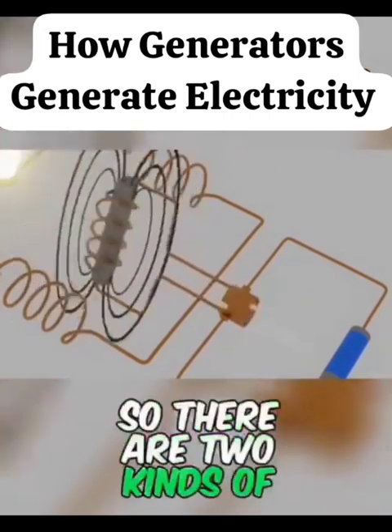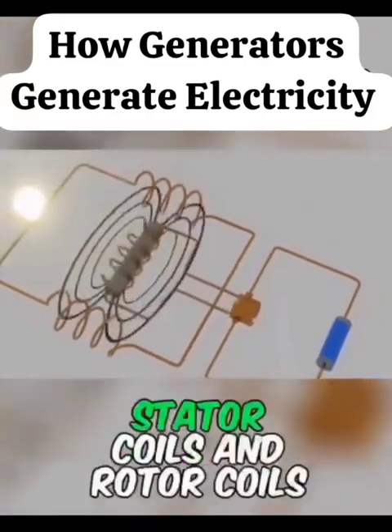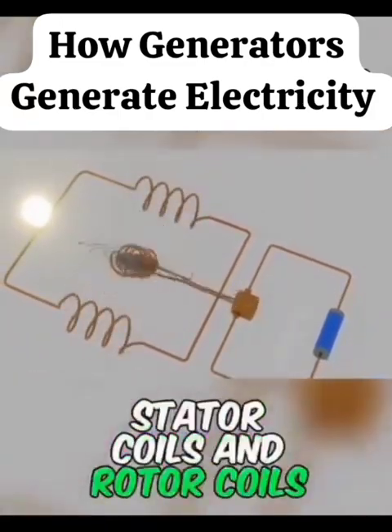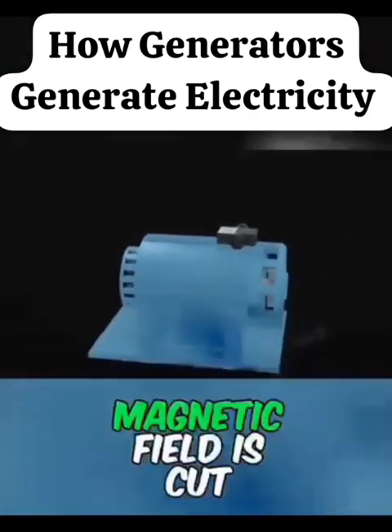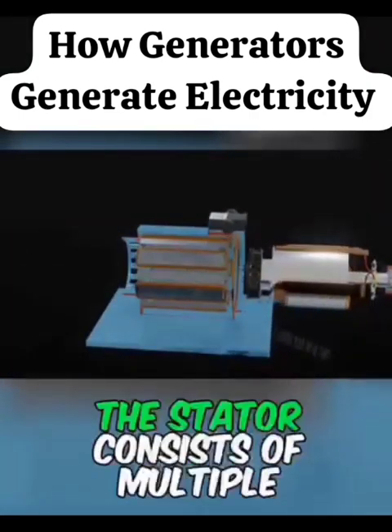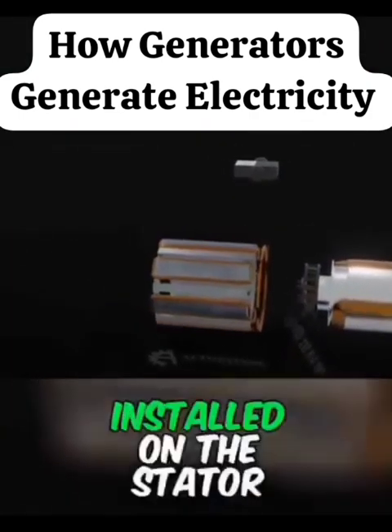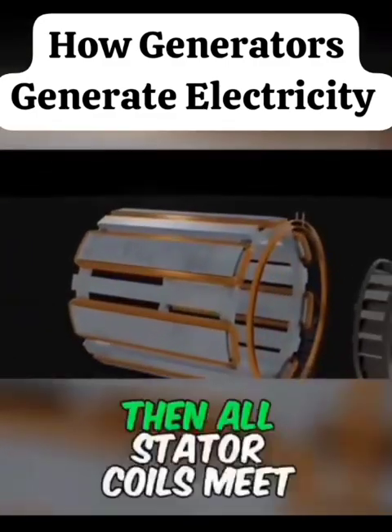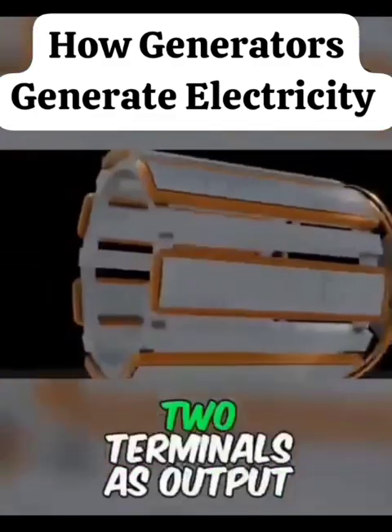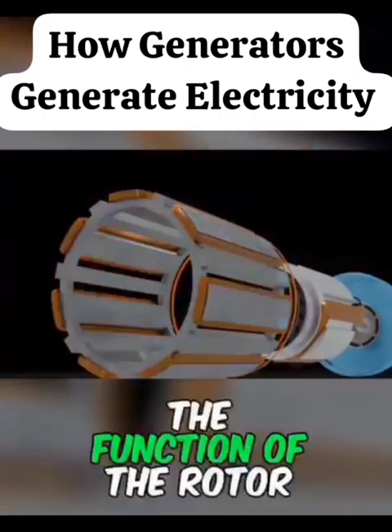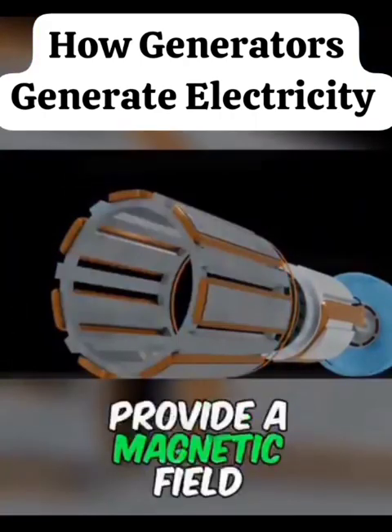So there are two kinds of coils in the generator, stator coils and rotor coils. The stator coil is where the magnetic field is cut. The stator consists of multiple coils installed on the stator winding. Then all stator coils meet two terminals as output. The function of the rotor coil is to provide a magnetic field.